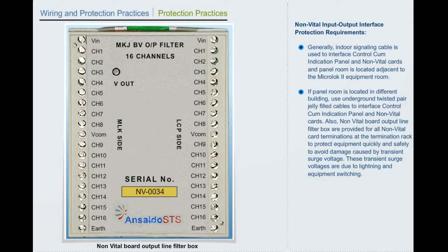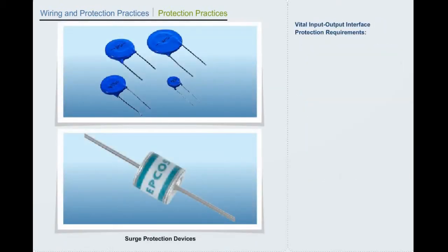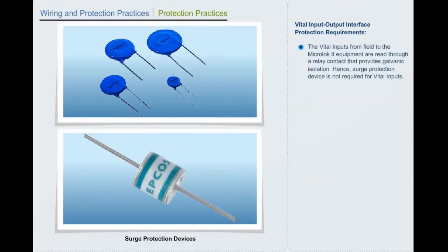Also, non-vital board output line filter boxes are provided for all non-vital card terminations at the termination rack to protect equipment quickly and safely to avoid damage caused by transient surge voltage. These transient surge voltages are due to lightning and equipment switching. Vital input-output interface protection requirements.